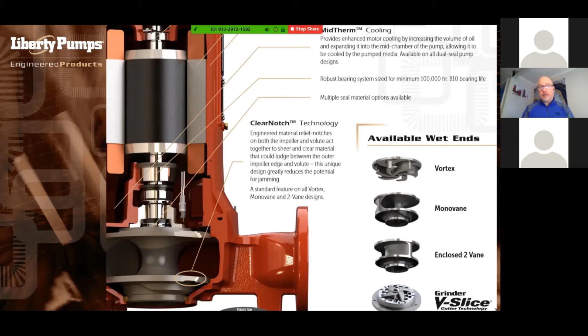I have a few other pictures coming up. We call these wet ends, but basically they're different impeller styles for solids handling. The dual seal pumps are a 3-inch solids handling pump, 4-inch ANSI flange. They are available in ordinary and hazardous location, and they have the seal sensing or seal leak detection probe. One of the impellers is a vortex design, and then we also have what we call a mono vane or one vane design, sometimes called a single channel style impeller. And then the enclosed 2-vane design is another 3-inch solids handling design. We also have the whole line of grinder pumps from 2.5 to 15 horsepower, which we'll talk about. Feel free to ask any questions either now or at the end, as any time is fine.